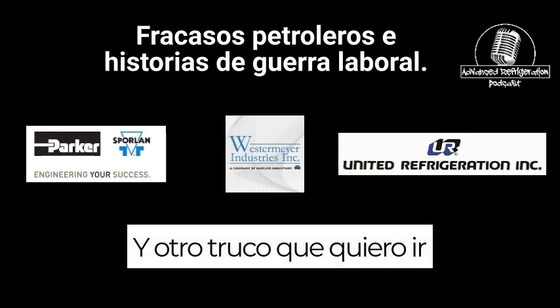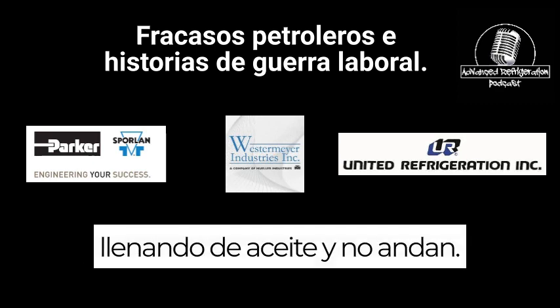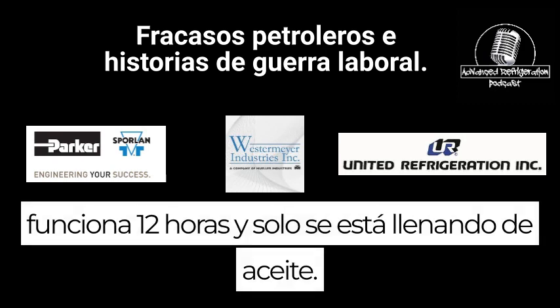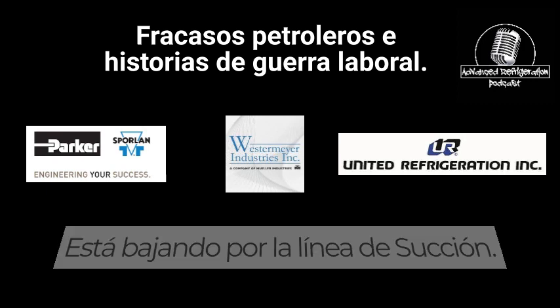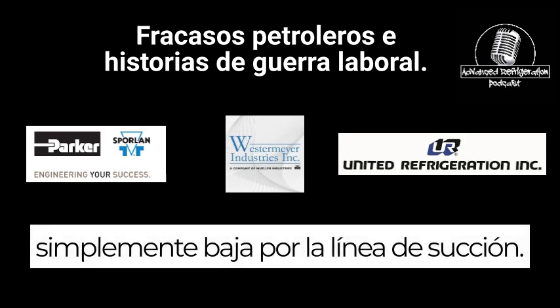And one other trick I want to go over is if you have compressors that are filling with oil and they're not running. Say you have an oversized rack and that compressor hasn't run in 12 hours and it's just filling up with oil. It's coming down the suction line. It's not coming from the oil flow, it's just coming down the suction line.